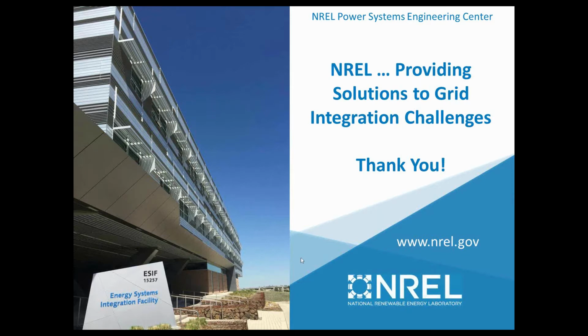Next. What are the trade-offs between trying to meet compliance for under-frequency load shedding and having frequency points that do not adversely impact a potential unintentional island? Well, obviously, this is something that really needs to be looked at. It depends where you have your under-frequency load shedding set points. Now, typically, those are going to be pretty low, 59.5 hertz or something. It could be different depending on your situation, but you probably do not want your DG trip points to be tripping above your under-frequency load shedding trip points. So you still want your DGs to be online.